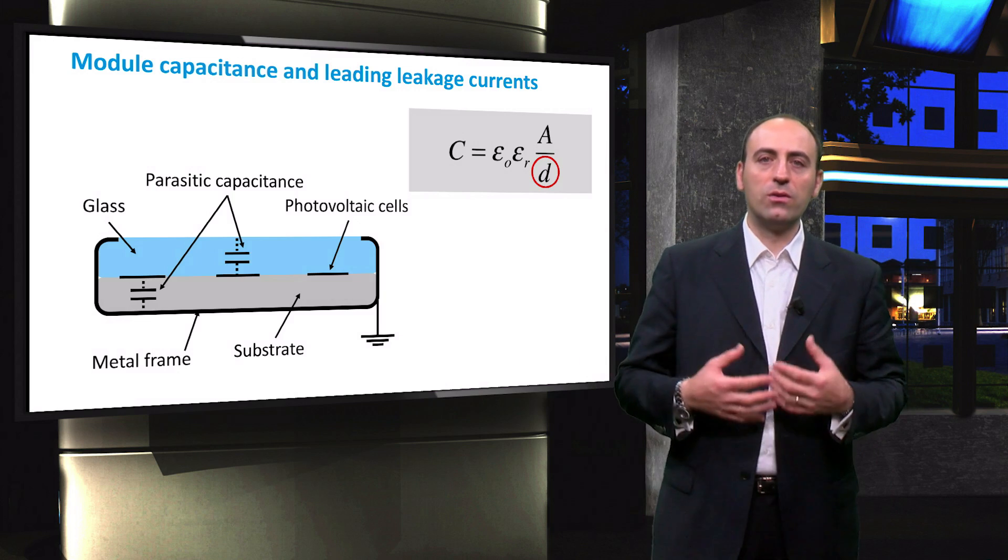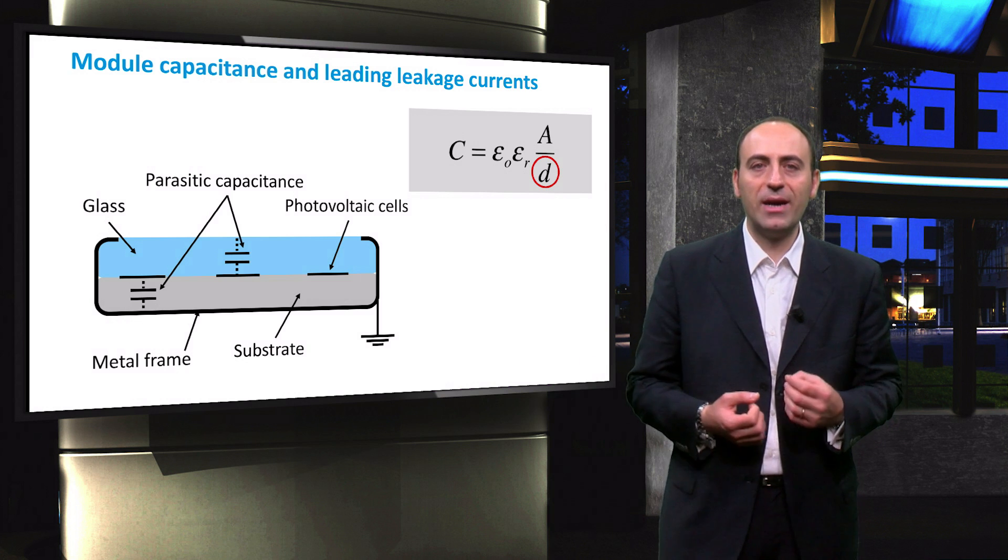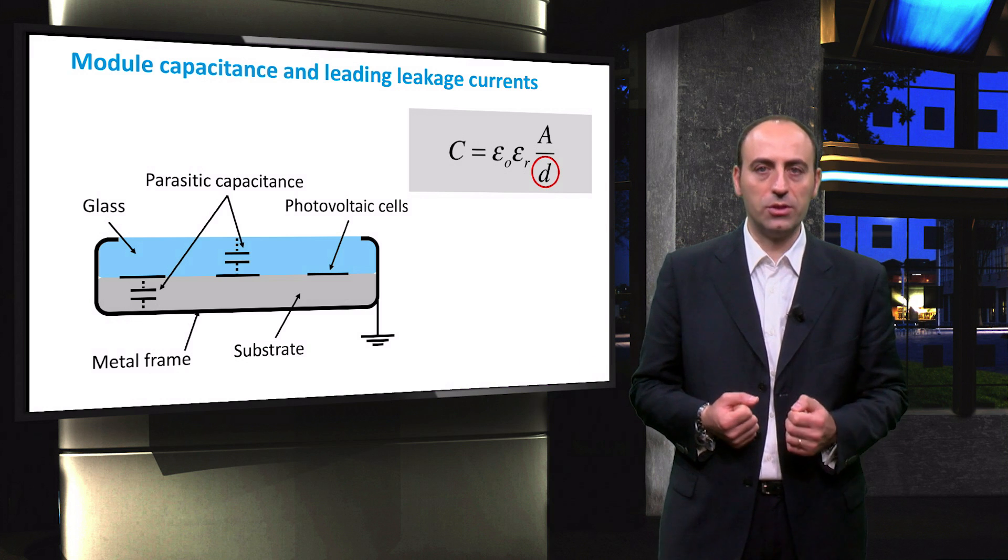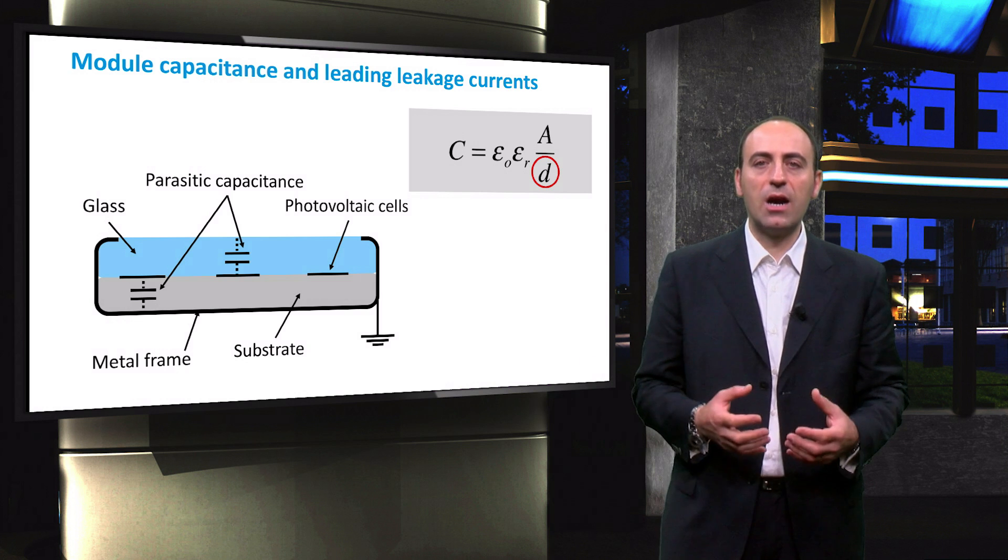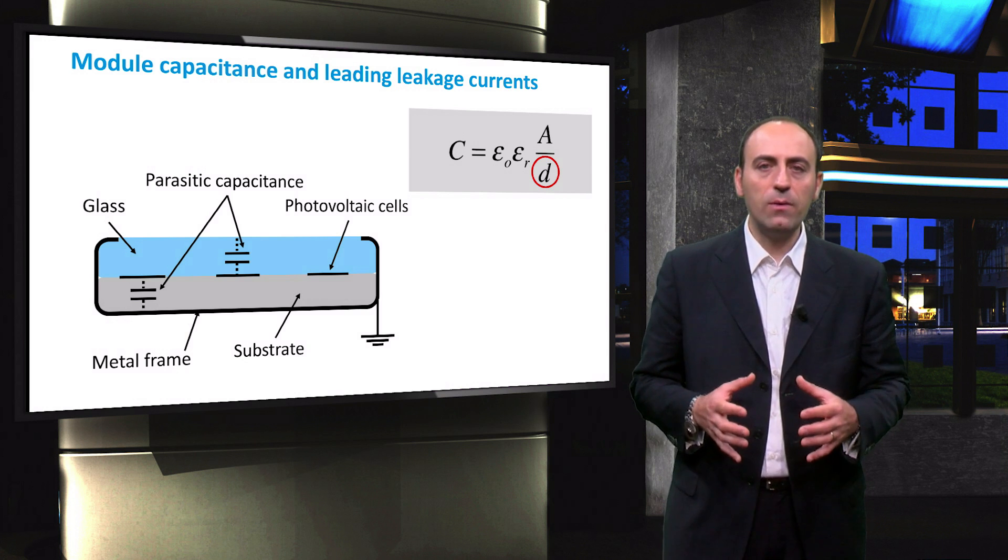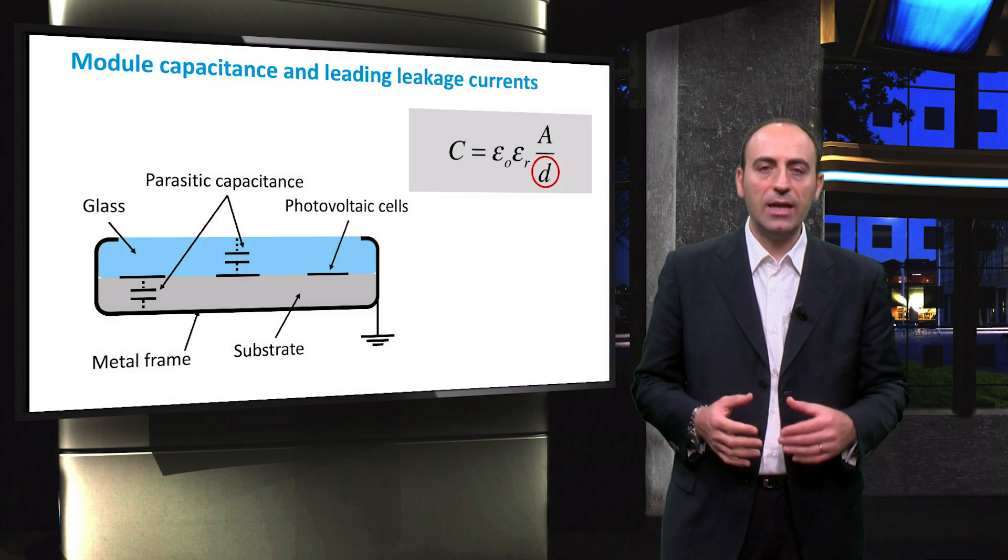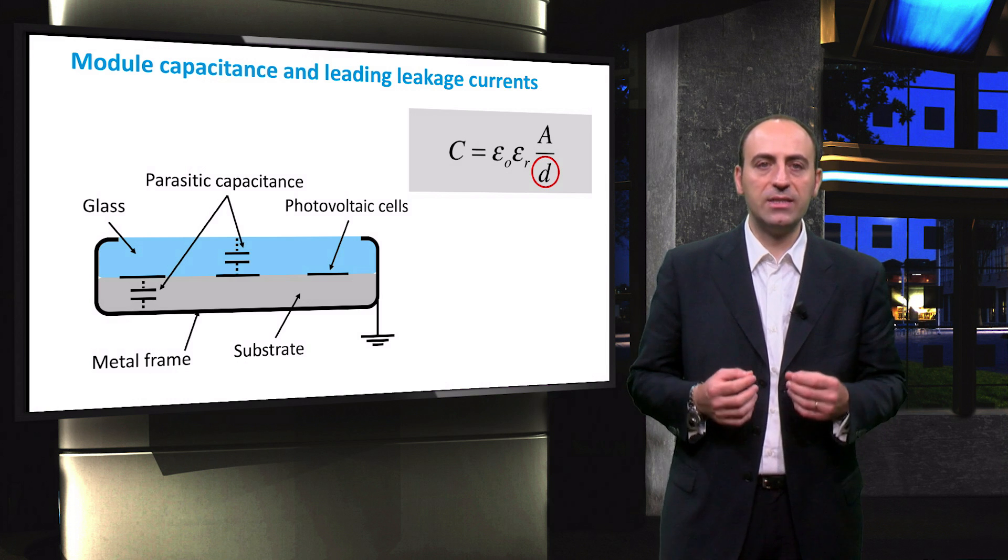Leakage current or discharge current is a reactive current, with its phase shifted by 90 degrees to the grid voltage. This means that this current is lossless and not dangerous on its own. However, this current can superimpose a possible residual current and obstruct its detection by safety devices.